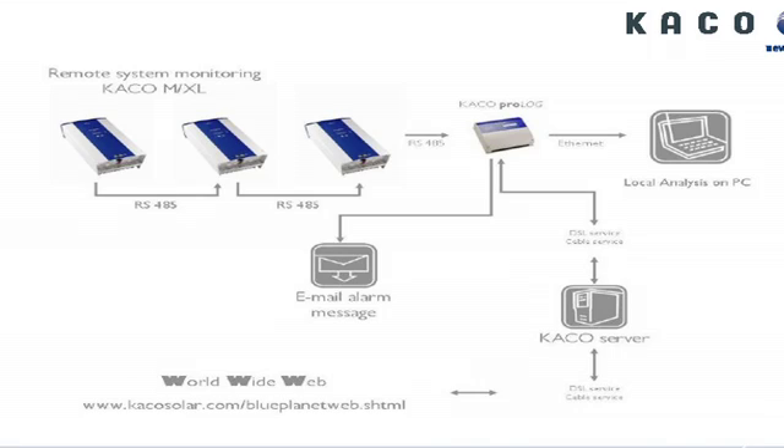This is the way you would set it up. You have an RS-485 setup, and the inverters are daisy-chained together — up to 32 — going into the proLOG. You can locally access the data as well as connecting it to our server. We will update the portal and you will be accessing it through the web, in this case through Sungevity's website.